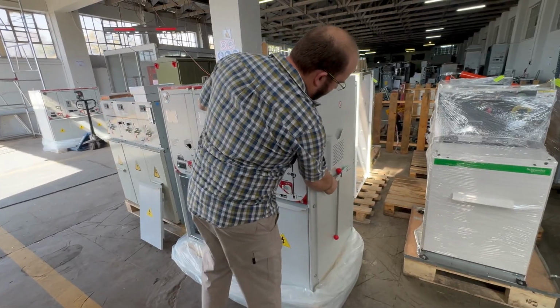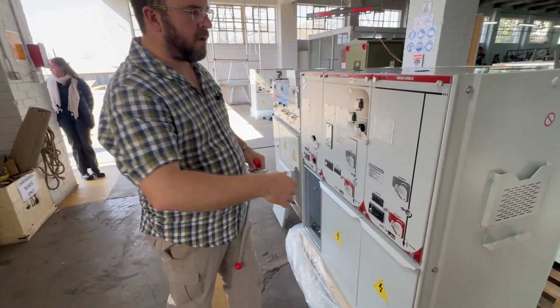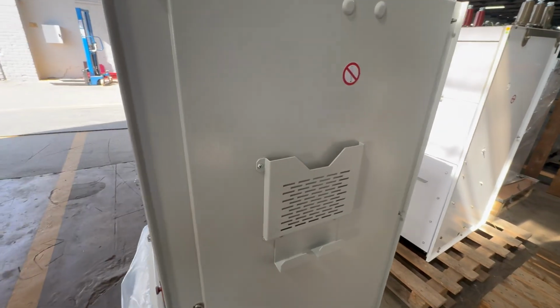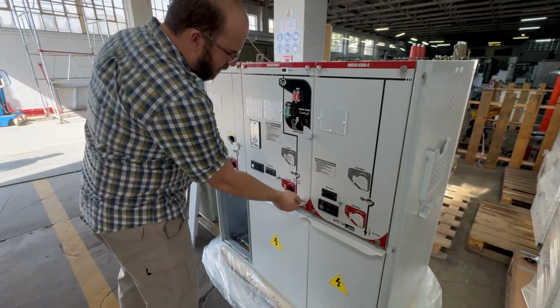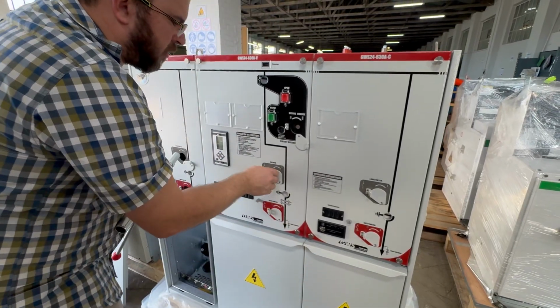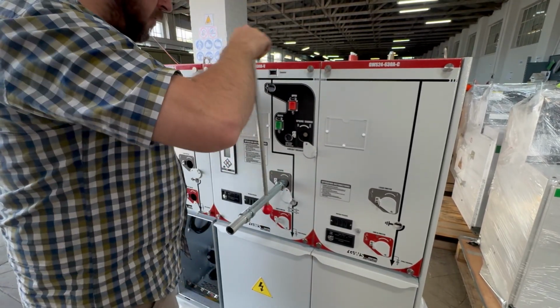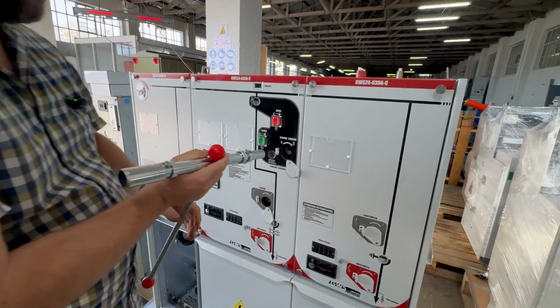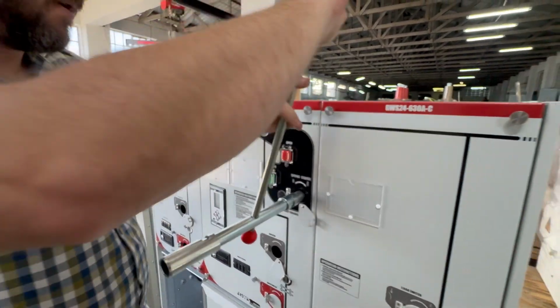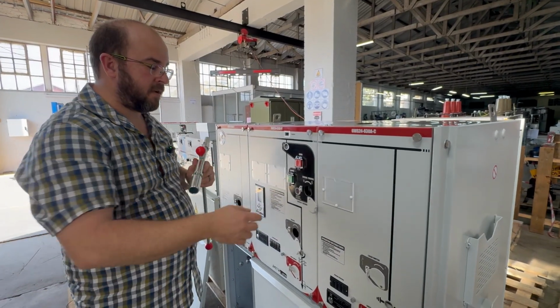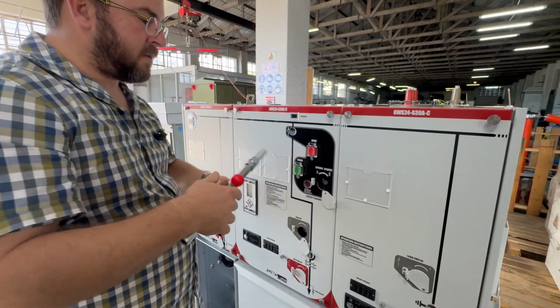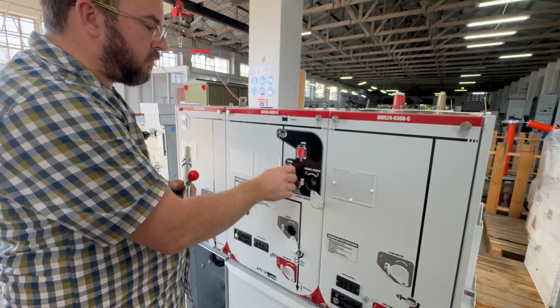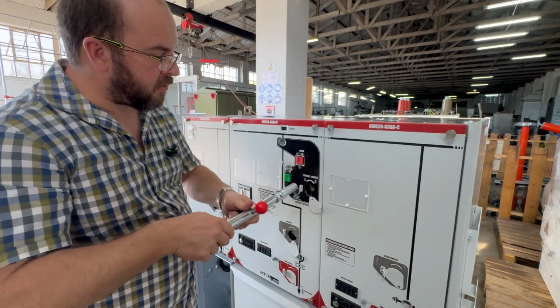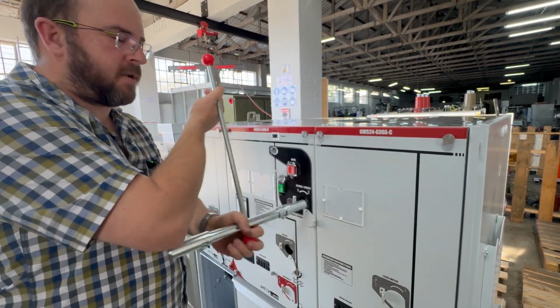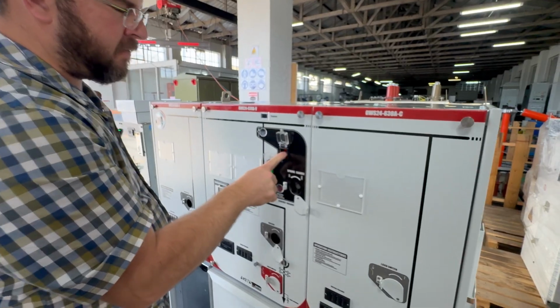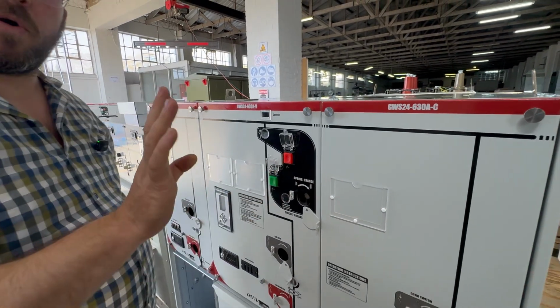So on the right hand side you will find your operating handle, always nice and helpful. And you will always have your documentation pack in there. Now first thing, you need to switch off your earth switch, and then you need to switch on your isolator. Wrong side. You need to switch on your isolator, and then you can now charge your spring charge on your circuit breaker. So it's so simple and so easy. There's no pressure. It is such a simple or easy way to charge it. Now you can close, and then you can actually charge it again. One hand operation, no stress. There you can actually open it, close it, and open it again, all with one charge.